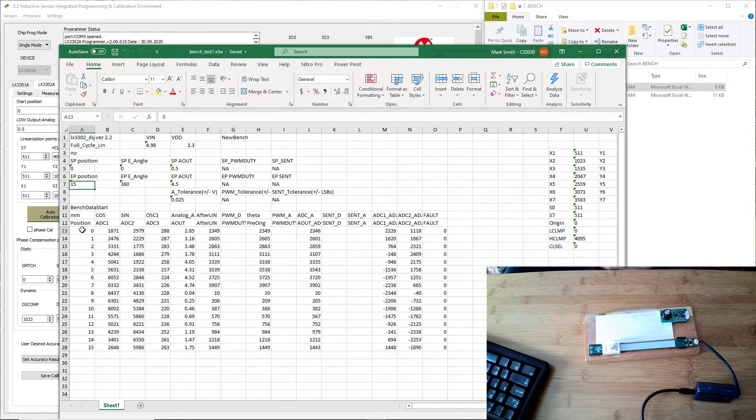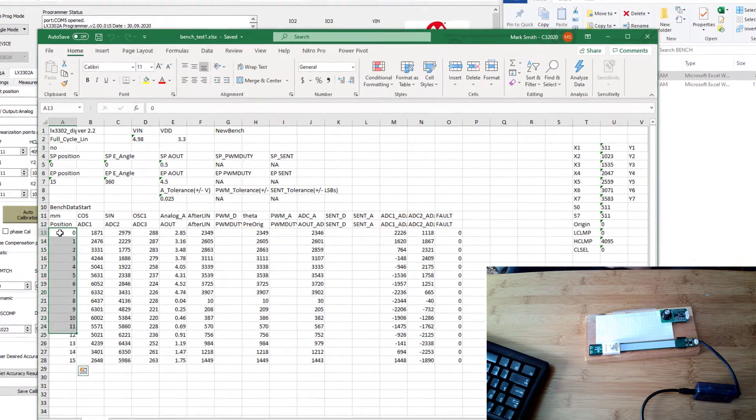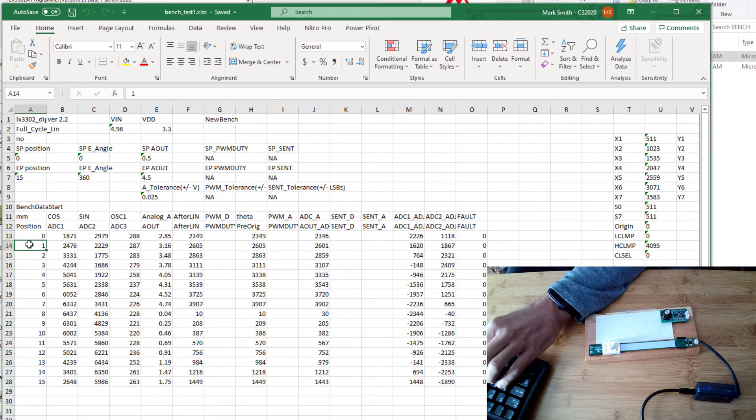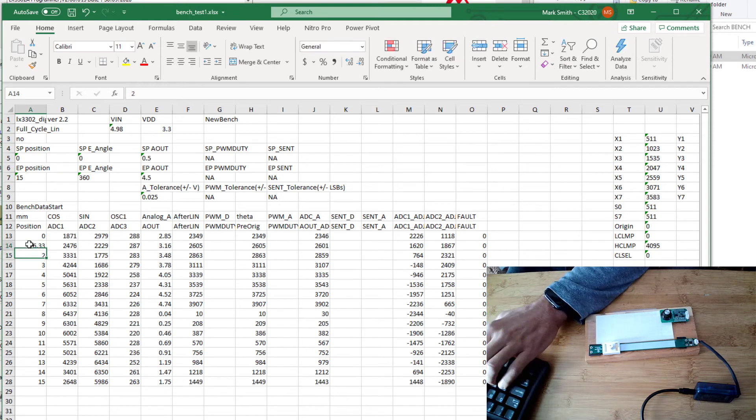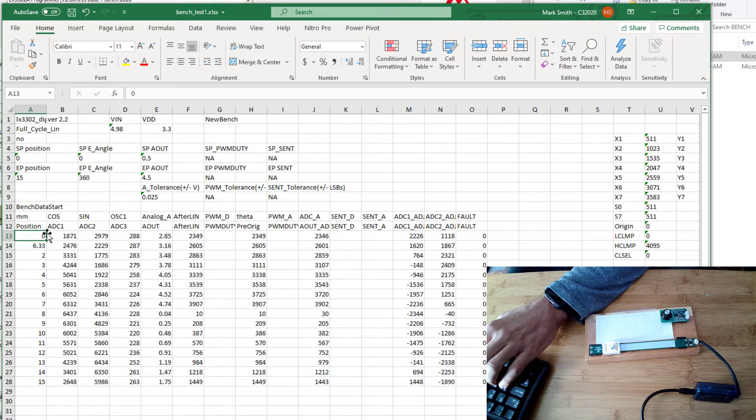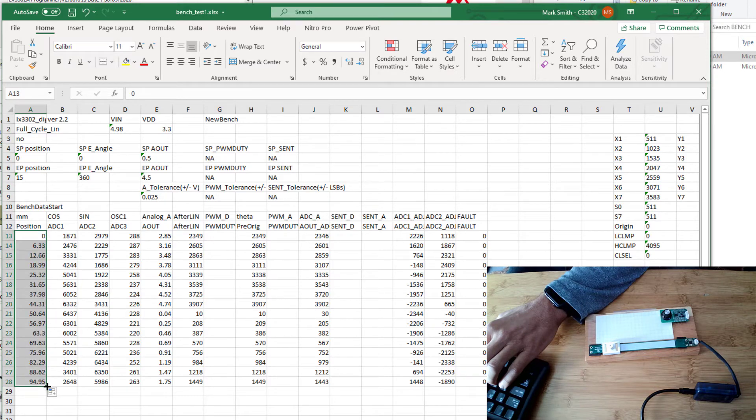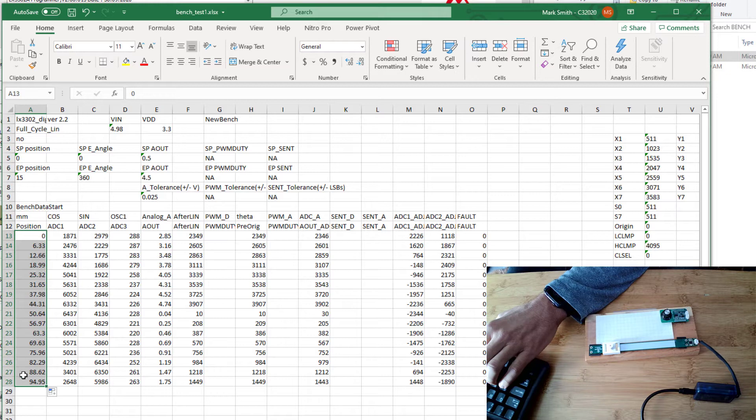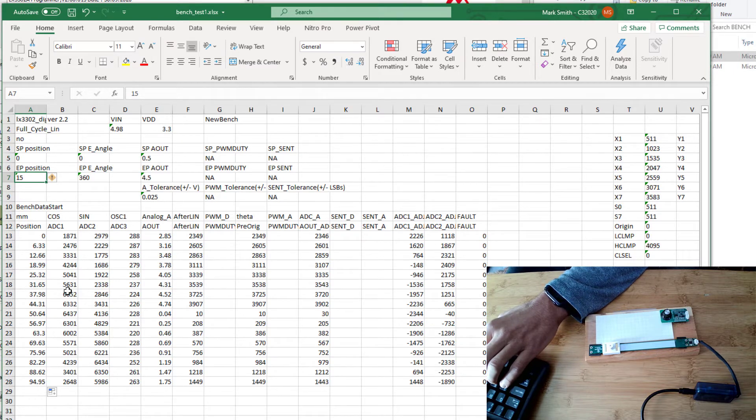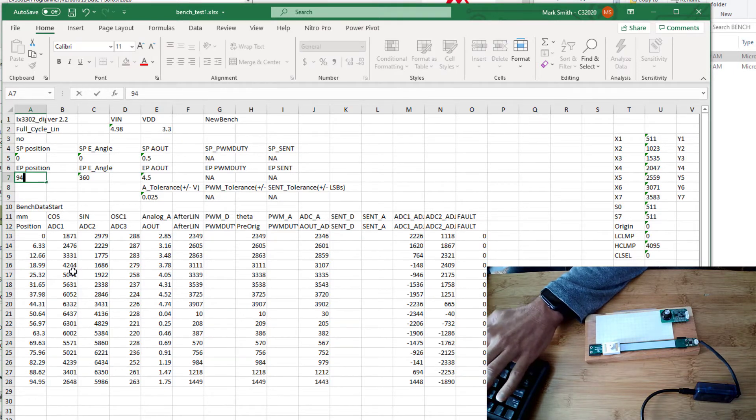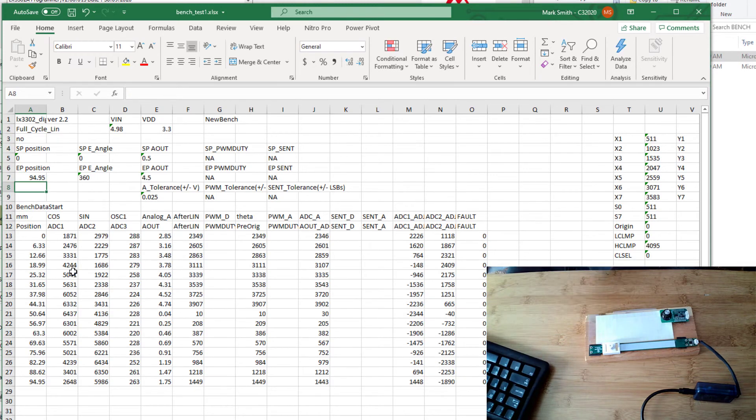You can actually see all those 15 positions we captured are shown right here. I could map these and change these if you wanted to. I can show you how to do that right now. That translates that from 0 to 15, to 0 to 94.95 millimeters. You also need to change this endpoint position to be the same value as the last point here, 94.95. Then we could do the same auto calibration that way.